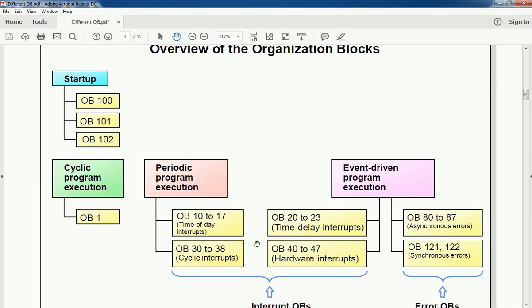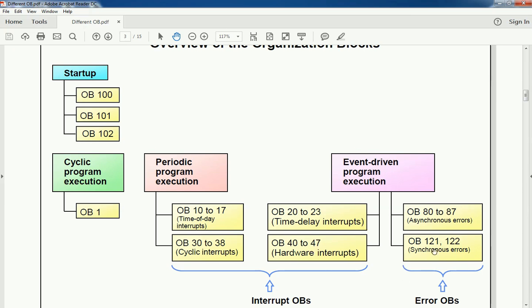All these OBs have different priorities. The highest priority belongs to error OBs — OB121 and OB122 have the highest priority, then OB80 to OB87, then hardware interrupt OBs, then time delay interrupts, and finally OB1 has the lowest priority. When any error occurs, the error OB will execute first, then hardware or time delay interrupt OBs. Every OB has a different priority, and based on that priority the instructions execute.